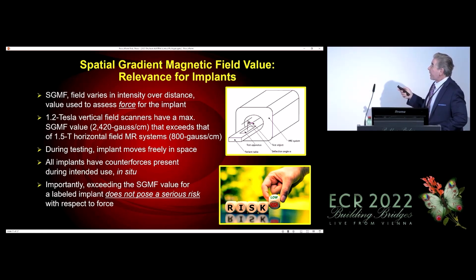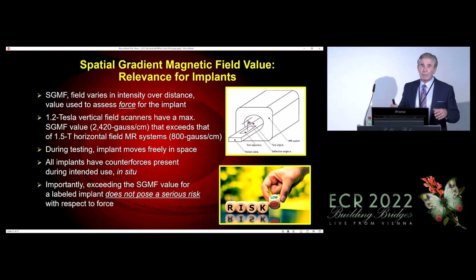And at that point, where the highest spatial gradient magnetic field is, which is the patient accessible value, because there's actually higher values if you get closer and remove the outer coverings of the MR system, we're really interested in what the spatial gradient magnetic field is for the patient accessible areas. So that's where the test procedure is done, and we measure a deflection angle. And depending on what that deflection angle is, we will then either calculate or extrapolate what the value should be in the labeling. But keep in mind that implant is freely able to move in space. That never happens when an implant is used in a patient. There's always counter forces present.